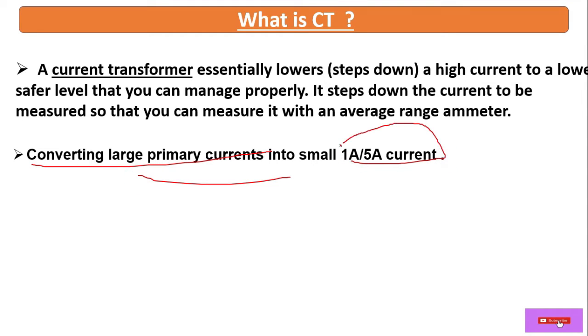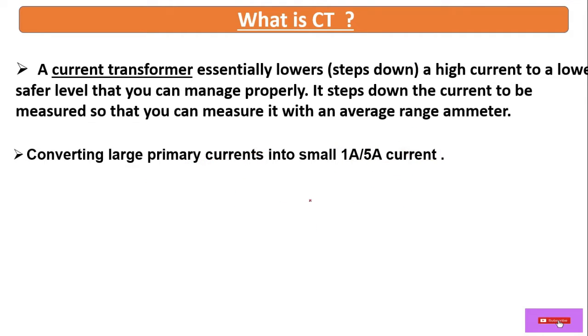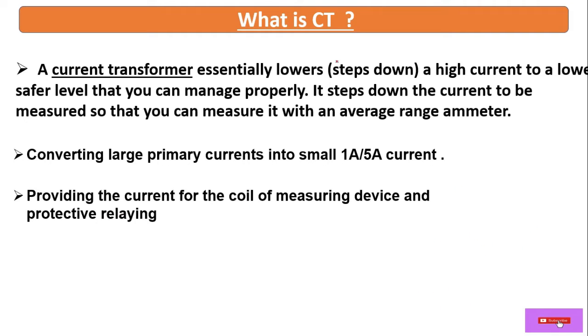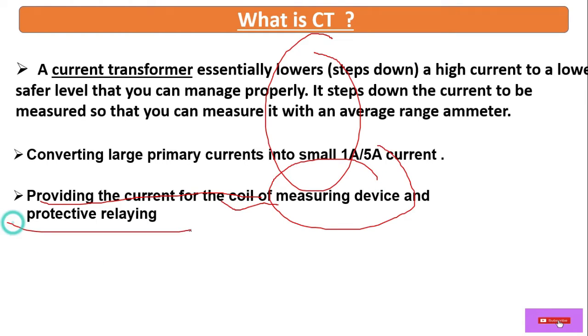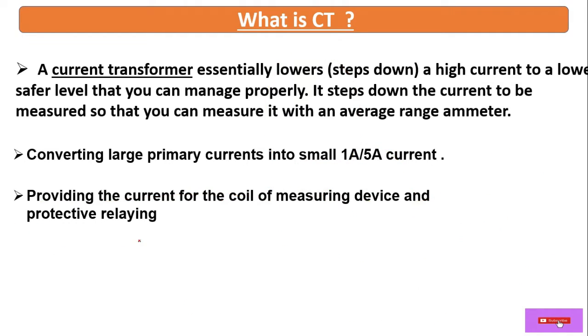So converting large primary current into one ampere or five ampere — this is the ratio of CT, which can be found expressed as primary current to one ampere or five ampere. What is the use of CT? It provides the current for the coil of measuring devices and protecting relay devices — for measuring devices like an energy meter, multi-function meter, or a protecting relay.